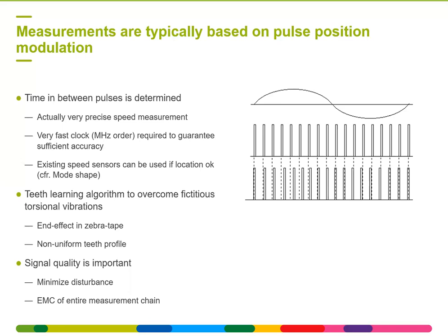If your machine is running without any torsional vibrations, the time in between two pulses will be uniform. So if you have torsional vibrations, then the time in between two pulses will start to vary, and you will see it in the measurements. So in the end, it's a very precise speed measurement. So instead of looking at the static part of your speed measurement, you're now looking at the dynamic part. So you're not looking at my machine is running at 50 hertz or 60 hertz. You're looking at what on top of this 50 or 60 hertz my machine is doing. And this is done by this typically pulse position modulation.